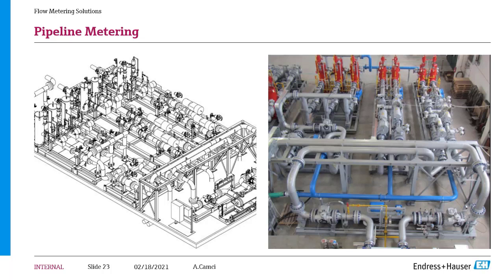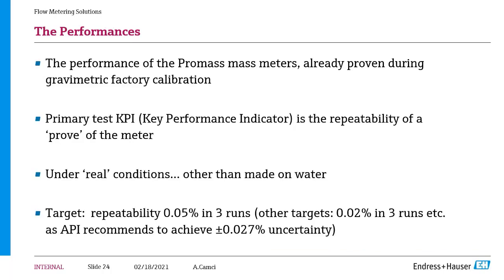In this meter, I mentioned the small volume piston prover. I would like to share some performances, to give you an example of how we can do better than the normative asks. The ProMass meters are already calibrated with gravimetric factory calibration, which is traceable up to the international standards, and delivered and installed in the custody metering system.